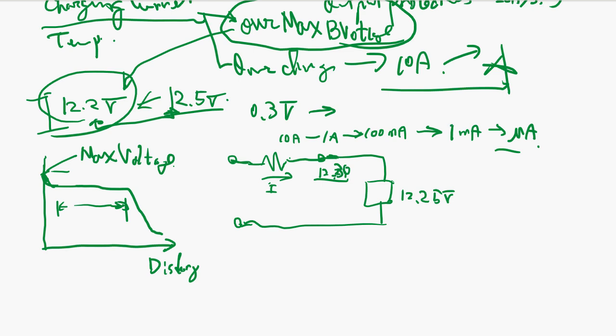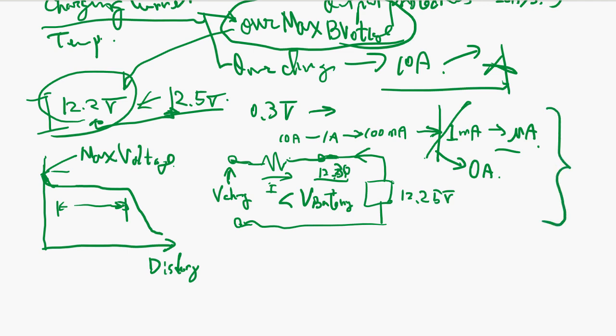So you need decision making - the CPU has to decide, okay, it's dropped to 1 milliamp, so we declare it fully charged. What do you do then? You drop the charging voltage slightly less than the battery voltage, so the current reverses back and is completely shut off to 0 amp. This is the ideal charging profile.